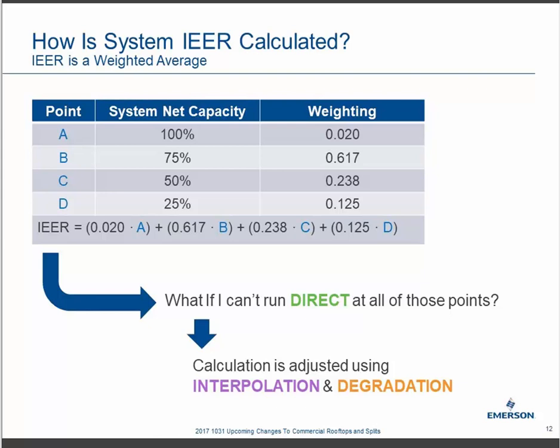Why are regulations moving toward a weighted average scenario? Early on, we talked about full-load rated equipment and EER-type measurement. EER at full load is advantageous for a utility managing peak loading. But IEER, SEER, and other seasonal weighted averages are much more representative of what's actually going on in the system and how it's consuming energy — which is valuable for contractors, channel participants, and end users. As Mike put it: 'I think seasonal weighted averages are good.